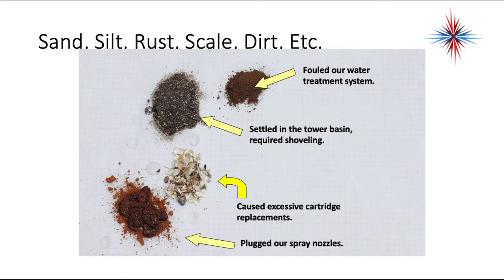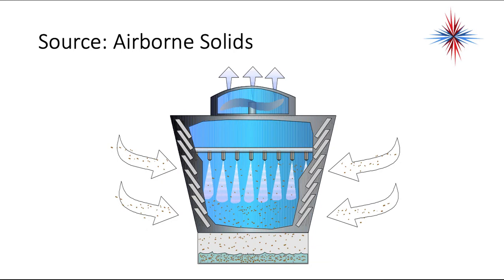Here are some examples of things that can be found in a tower system: a fouled water treatment system at the top, settled solids in the tower basin requiring shoveling, excessive cartridge replacements, and plugged spray nozzles with what looks like rust and iron buildup. Some contaminants come in through airborne solids — things in the air being pulled into the tower that contaminate the water and settle at the bottom.